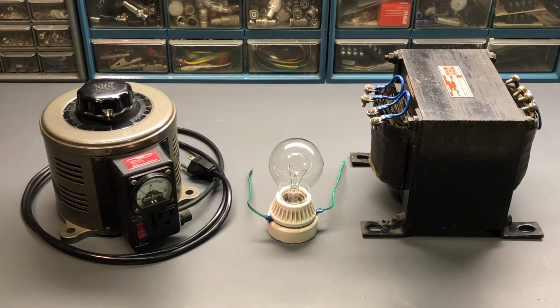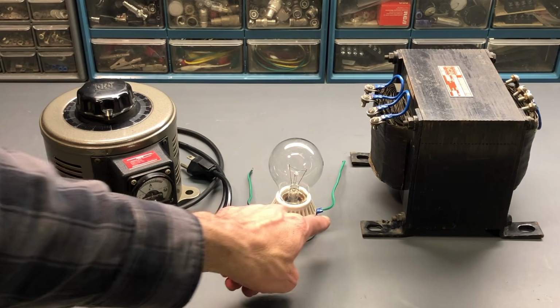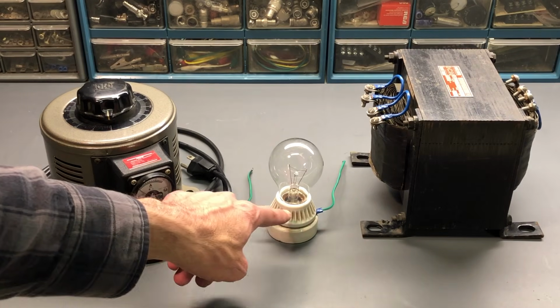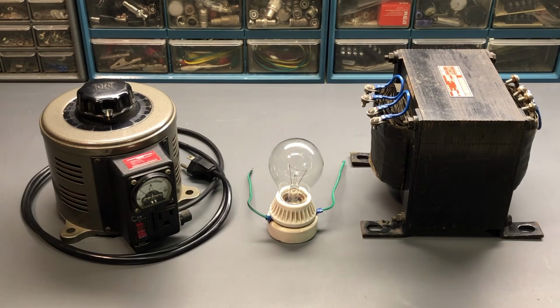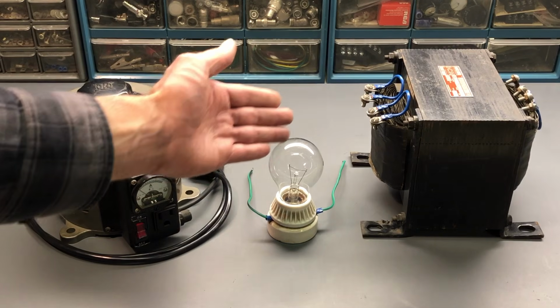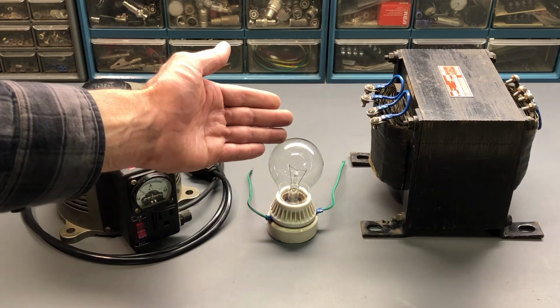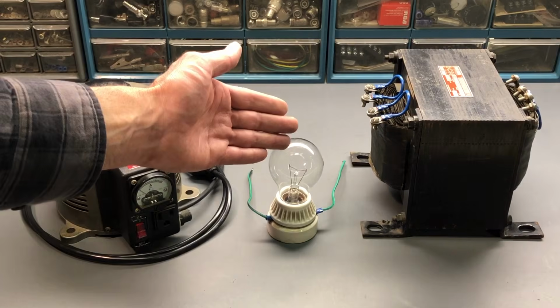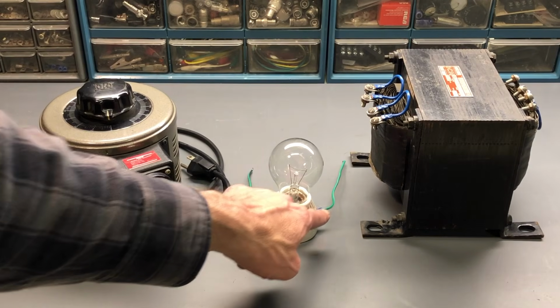Now, in my tester, a feature that I would recommend is to have a switch across the bulb that takes it out of the circuit by shorting the bulb out, because when you're testing a piece of equipment and you want to bring it up to full line voltage and you know that it is in good working order, you no longer need the current limiting offered by the bulb, and you want to take the bulb out of circuit. So if you have a switch that just shorts across the bulb, it is out of the circuit.